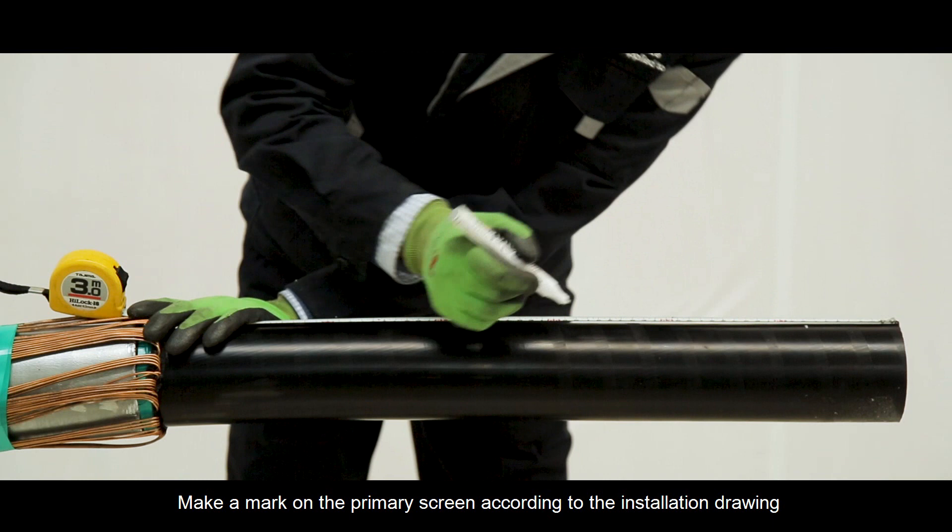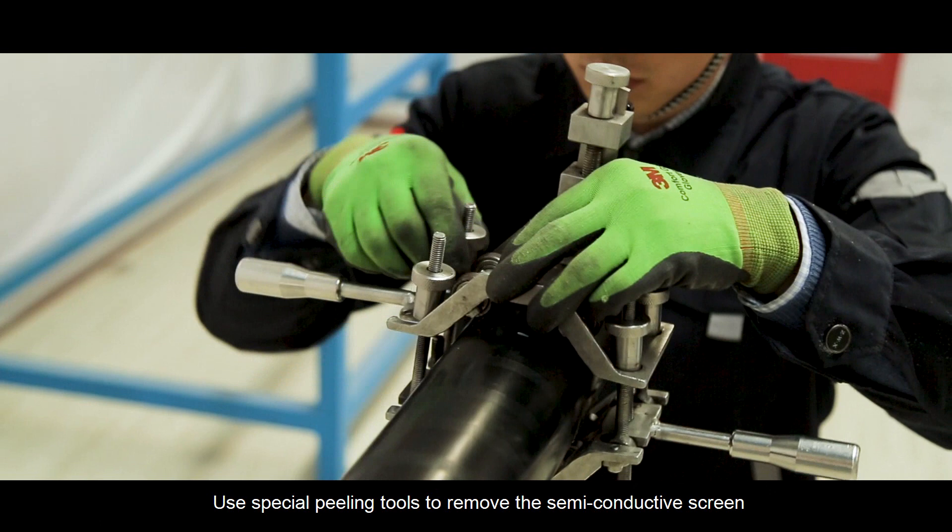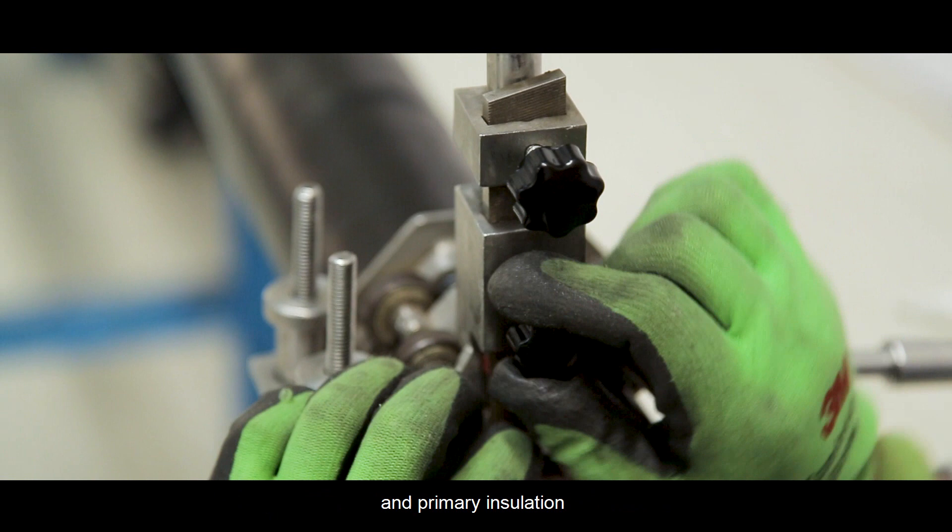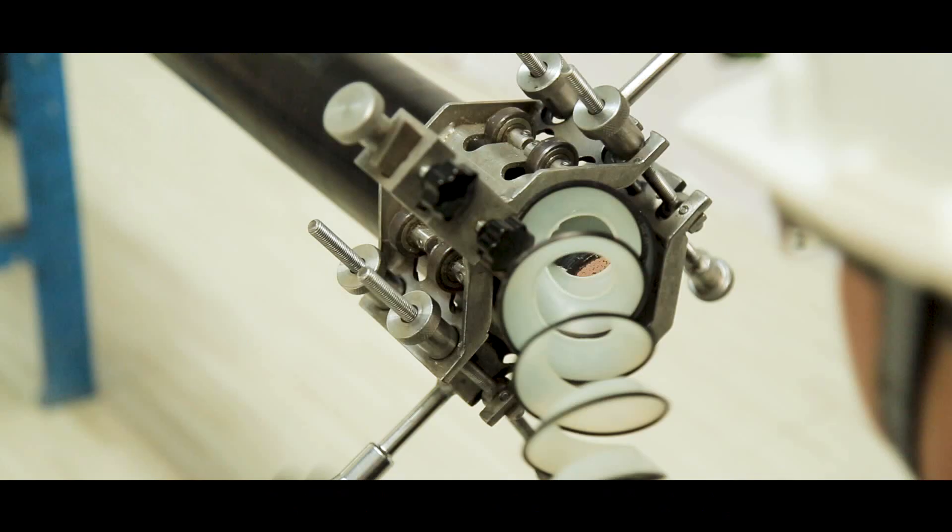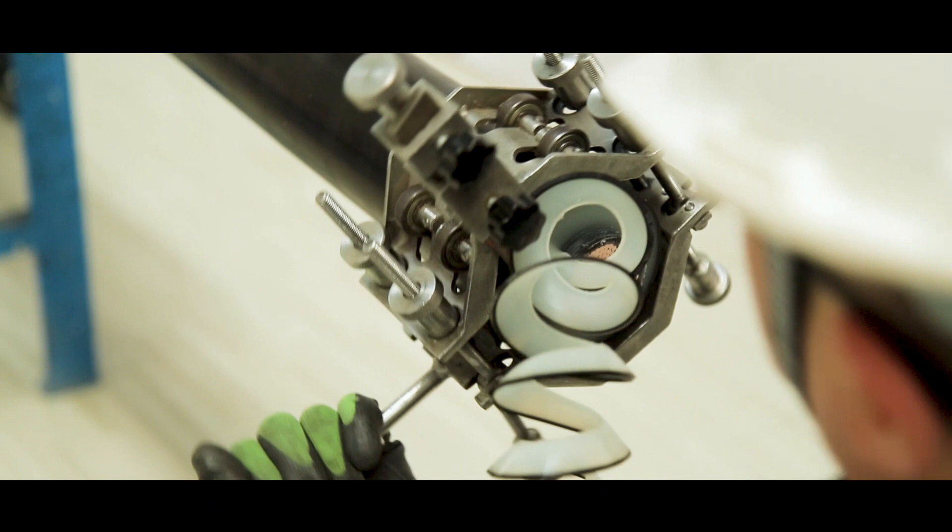Make a mark on the primary screen according to the installation drawing. Use special peeling tools to remove the semi-conductive screen and primary insulation according to the dimensions given in the installation drawing.